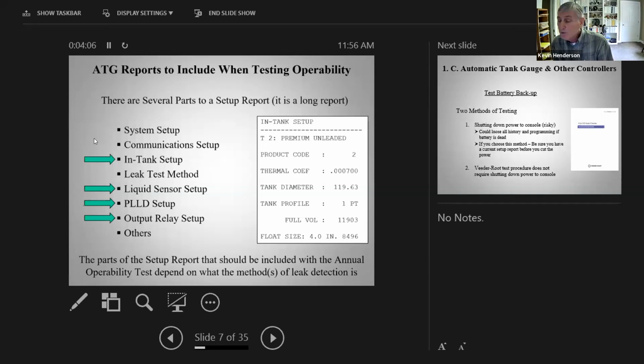You have sensors connected to the tank gauge, and obviously you want to have the liquid sensor setup portion of the report. If you have PLLDs, there's a little section of the setup report that deals with PLLDs. And if you're doing STP shutdown, there is another part of the report that has the output relay setup. So again, it just depends on what you have as to what parts of that report you need to make part of your annual operability testing report.